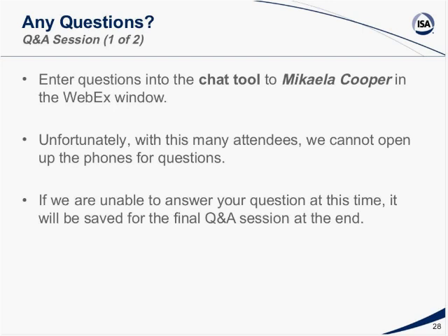Next question. Which particular code and clause requires one logic solver per boiler? It's in the NFPA code. It's part of the definitions in NFPA code 85.